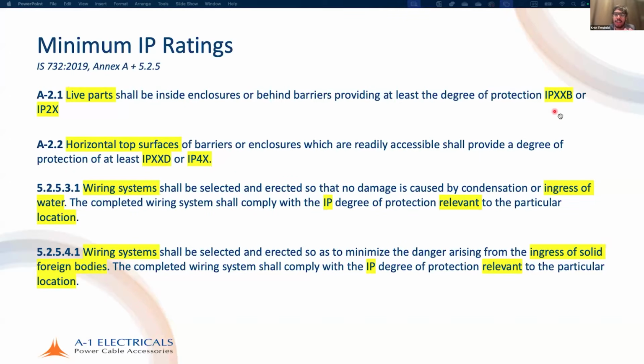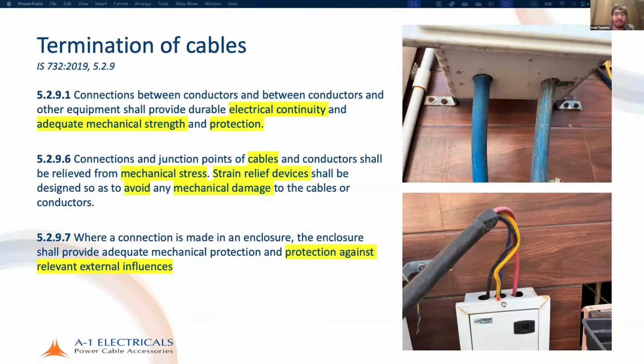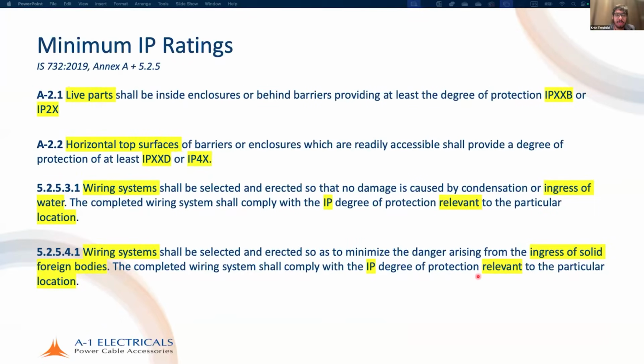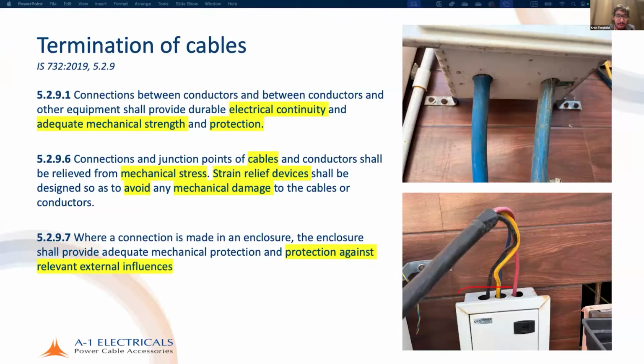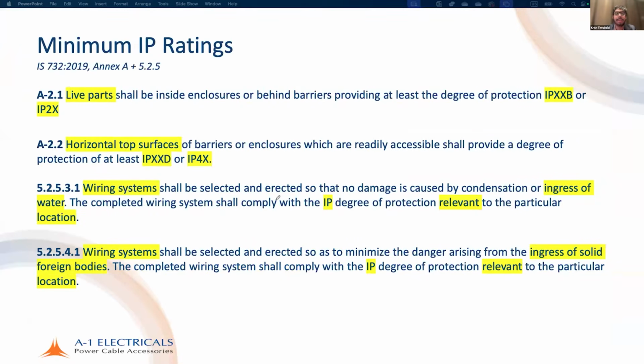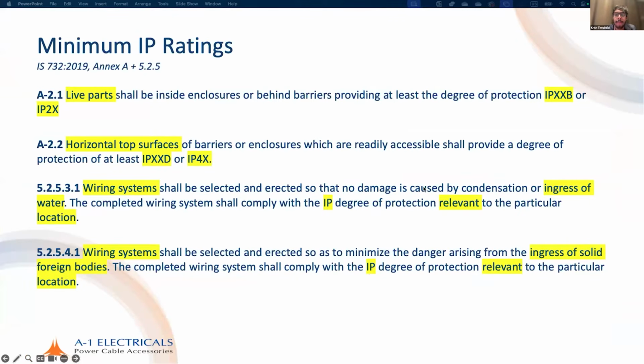IPXXB is specifically for protection against a finger. IP2X is also for the solid foreign body. So IP2X covers the 12.5 millimeter solid body plus the 12 millimeter diameter finger, while IPXXB is only the 12 millimeter diameter finger. Now, the important part is the horizontal top surface, right? So that is this horizontal top surface here, for example. If I just scroll in, I'll show you. This is the horizontal top surface that we have right here. I'll just highlight it with a pen. For horizontal top surfaces, the requirement is IPXXD or IP4X. Now, IPXXD means protection against access by a wire. So a 1 millimeter diameter wire that is 100 millimeters in length should not be able to penetrate this object.